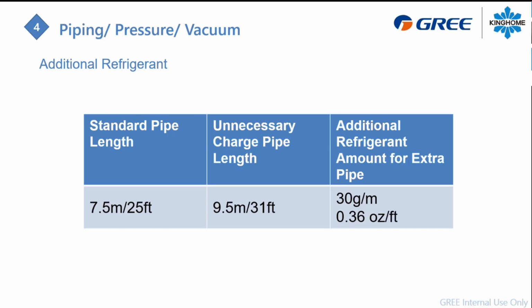The system is pre-charged for 31 feet total. Standard line pipe length is about 25. The minimum is 10 feet, okay? You will not have to remove refrigerant from it because the system already uses a liquid cylinder that will hold the charge right here, and you have your accumulator that will protect the compressor, so you don't have to remove any charge of refrigerant. The system is already good for 31 feet. If you have more than that, you will need to add refrigerant.